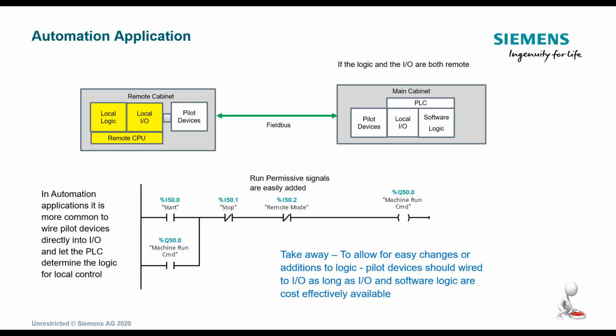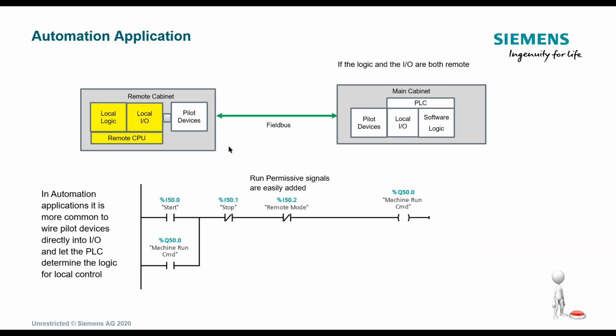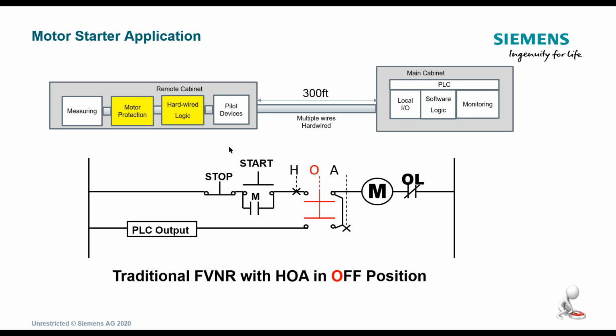You'll understand that a little better with SIMOCODE here in just a minute, and I'll show you what I mean by that. To allow for easy changeover in logic, it helps to be able to move that out in the field. You're cutting down wiring and terminal blocks and costs and so forth with it. Okay, so here's a traditional full voltage non-reversing hand-off-auto of the main PLC, the remote cabinet, and the hard-wired logic. And this could be a motor control center, or this could be just a control cabinet.